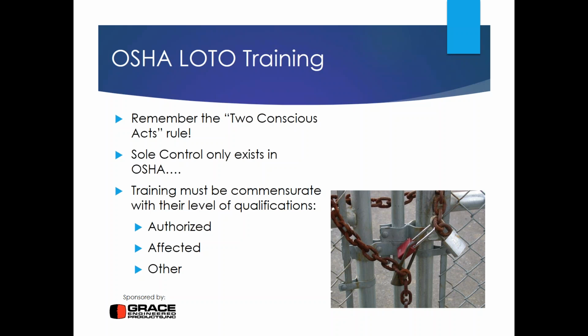Again, this is all about probability. Dan is going to talk to you a little bit about hazard analysis and risk being a function of both severity and probability. In this case, the logic is that requiring two things to be done on purpose is going to eliminate absent-minded or accidental reclosures, and it's going to require somebody to purposefully do something. And of course, the need to cut off a lock would also preclude anybody from inadvertently doing that. It would be a required purposeful act.